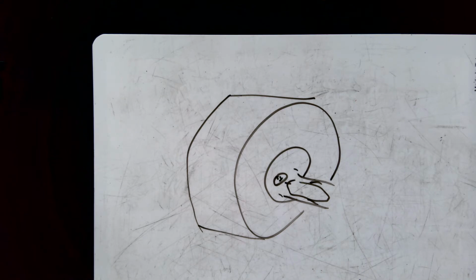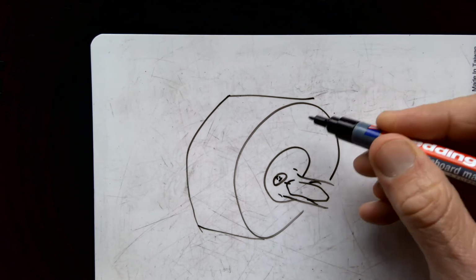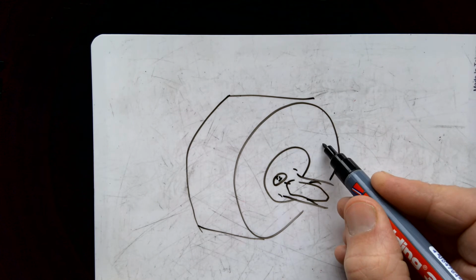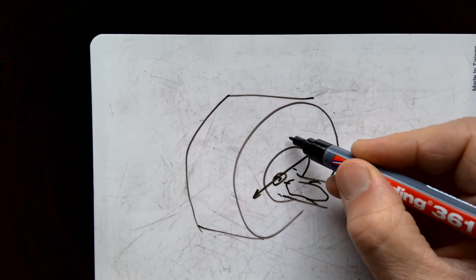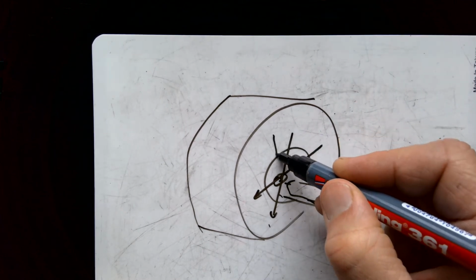Okay, so what we've got going on is that instead of our normal system where we just have a fixed head and you fire the X-rays through and the detectors underneath, what we've got is your X-rays will pass through, and then the position of that source changes and they'll pass through at a different direction.